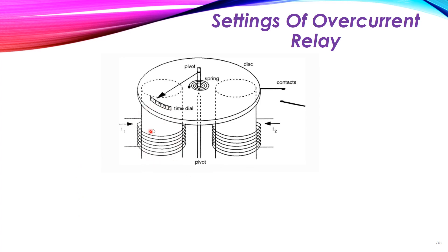As you remember, the induction disk consists of two poles, each taking currents i1 and i2, which produce two fluxes phi1 and phi2. The angle between these two currents produces an angle alpha between the two fluxes, which leads to the production of torque inside the induction disk.